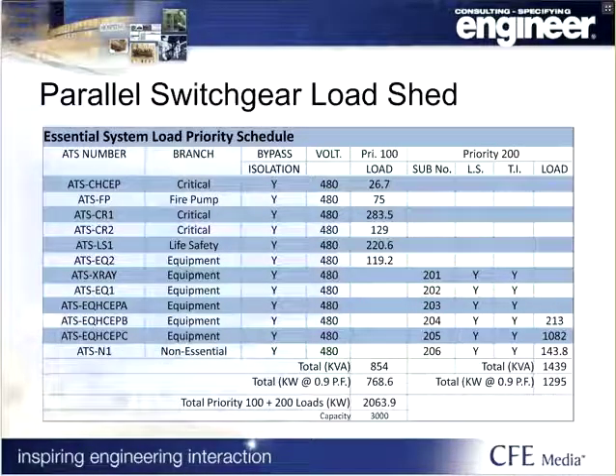And you can see that we've got the critical branch. This is a hospital that is in Florida. We've got the critical branch, which has a load on it, and fire pump, life safety. Those are all necessary loads. The equipment 2 branch in this case was a smoke control system, which is required to be on in 60 seconds, so it's part of our priority 100. That means that you cannot shed that load as part of this layout. We have X-ray, some chillers, and some air handlers, and then we have the normal system.